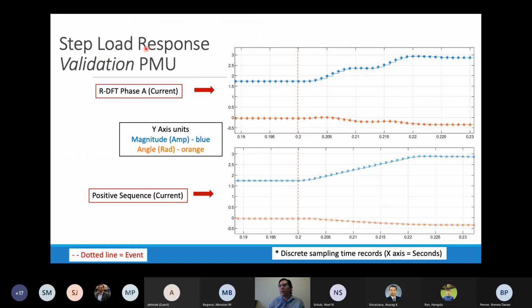So when we have a step load, I'm showing in the blue line the magnitude and in the orange one the angle. When we have a step load that happens at 0.2 seconds, we can see how the response settles down in a matter of a cycle, thanks to our recursive DFT full mode, in order to reach steady state. But we can detect at the earliest stage that we are having some eventuality thanks to our frequency rating in the early time. So here I'm showing the recursive DFT response at the end of phase A.